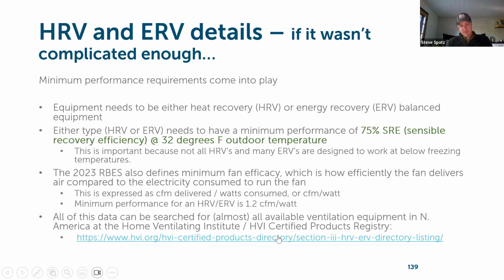So the fan efficacy side of the equation is something that you would have to look into beyond what's usually provided by submittal data from manufacturers. The CFM per watt is basically dividing the amount of CFM delivered by the amount of energy, electricity, run to the motor to deliver that CFM at 32 degrees.